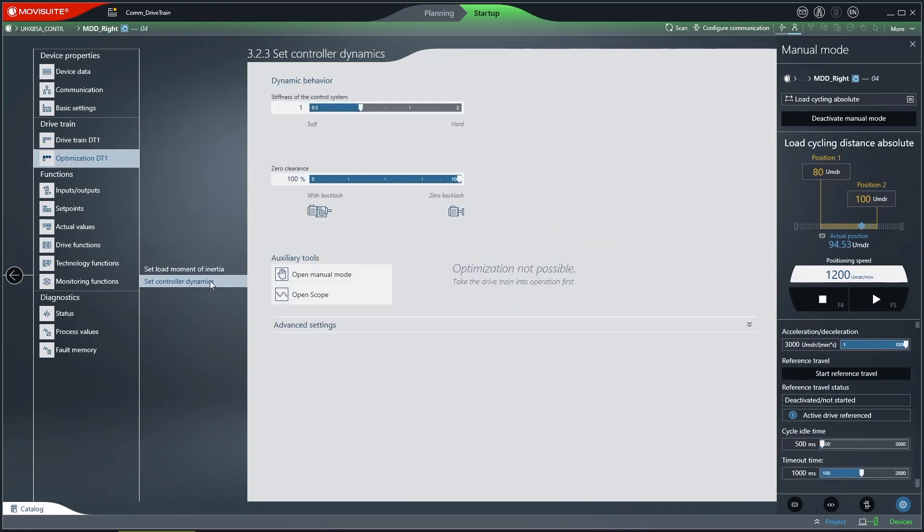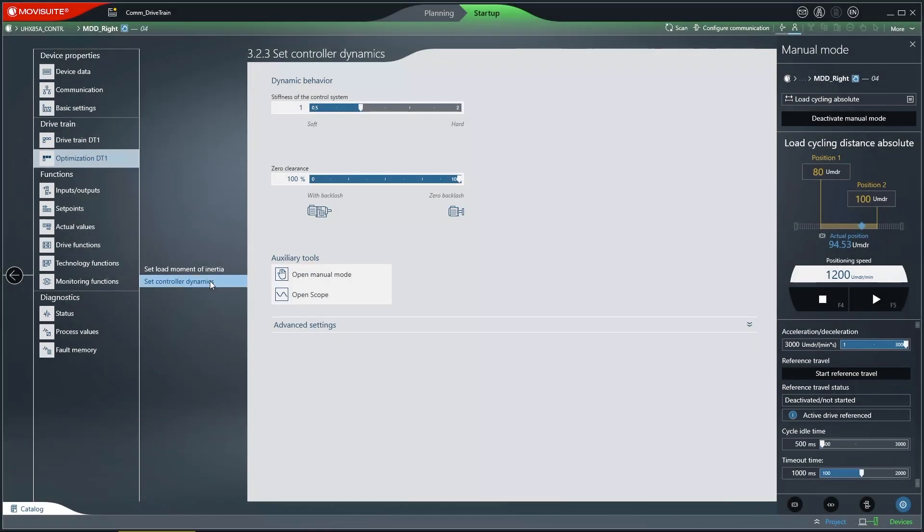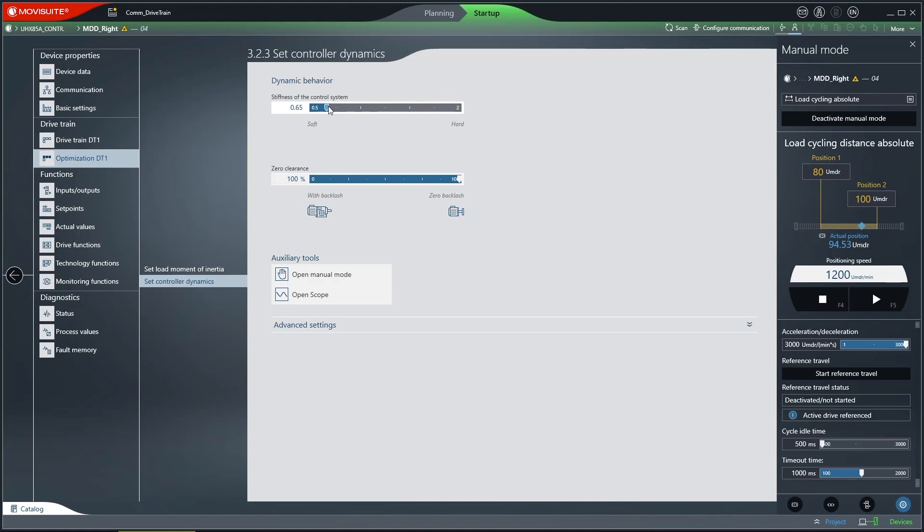You can change two values in the controller optimization section, namely the stiffness and the clearance. Use the stiffness slider to set the stiffness of the speed controller. The default value that can be maintained for most applications is 1. Use the clearance slider to set the clearance level of the drivetrain.